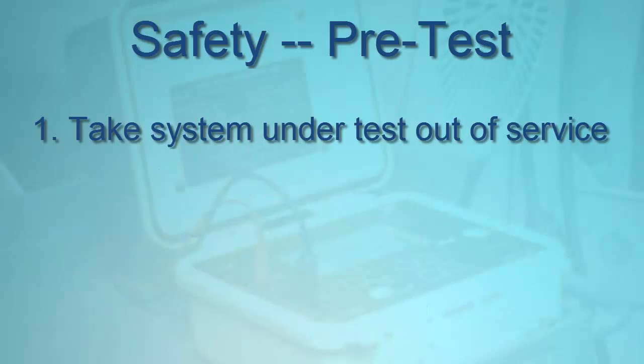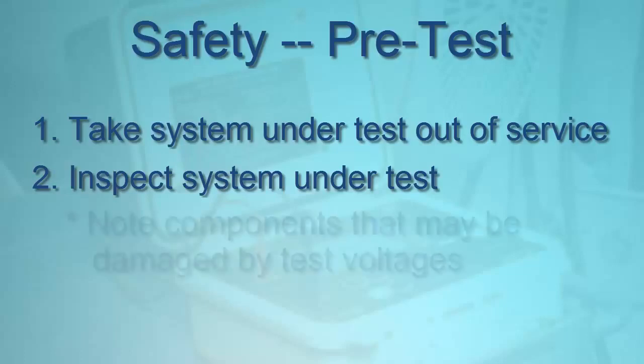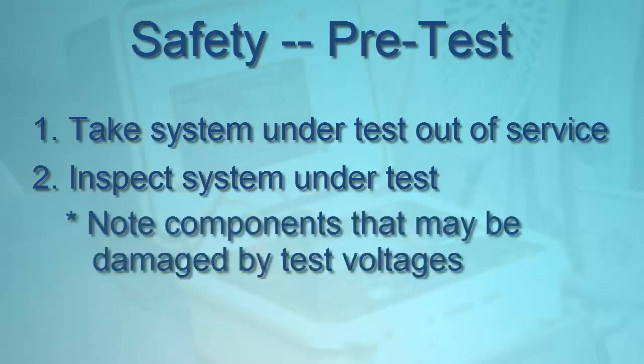Next, perform a thorough inspection of the system under test. In general, the more equipment included in the test, the lower the resistance rating. Therefore, it's critical to inspect the system and understand exactly what you're including in the test. Make note of any equipment that might be damaged by high test voltages, and either adjust the test voltage accordingly or exclude these components from the test.